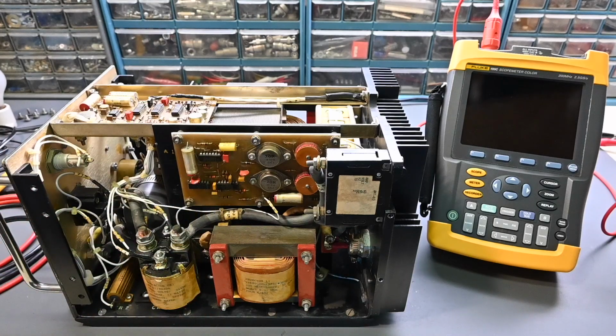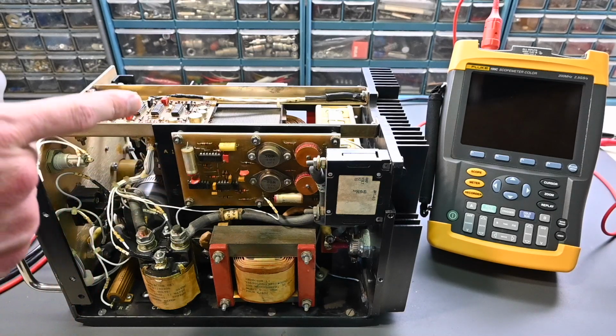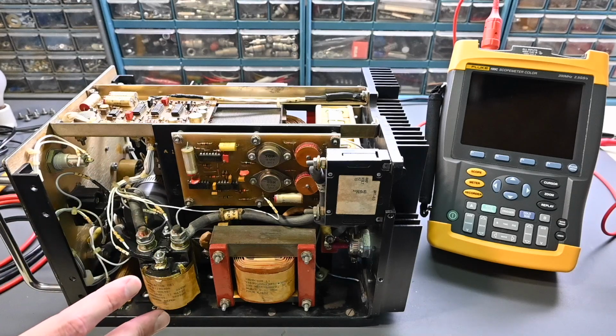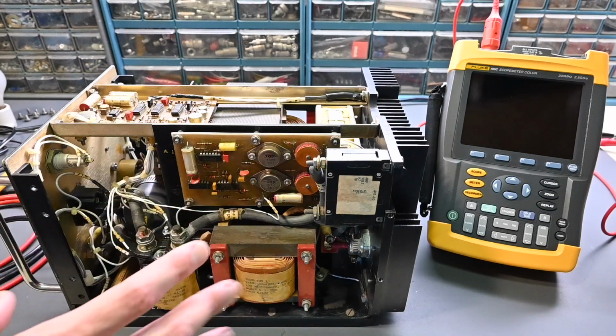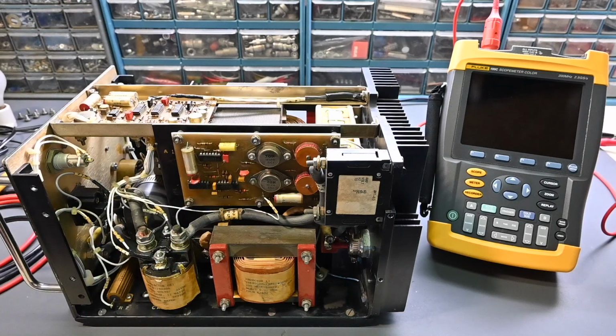In the first video, I mentioned there's a 600 volt tap on this main power transformer, and I didn't know if it was used or not. It seems like a very high voltage for this inverter - nowhere does this output any kind of voltage like that. It is actually used, so I don't know the function, and if anyone has ideas, please post them in the comments. After this first test, I'll turn the inverter on its side and show you where that tap is connected. It seems unusual - I don't really know the design idea behind what they're doing with that 600 volts.